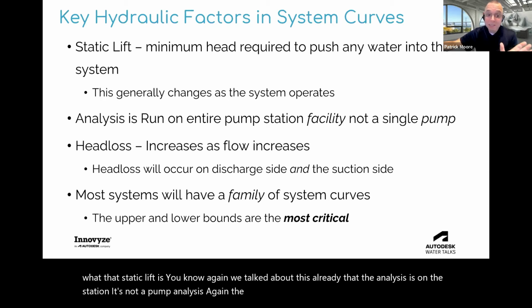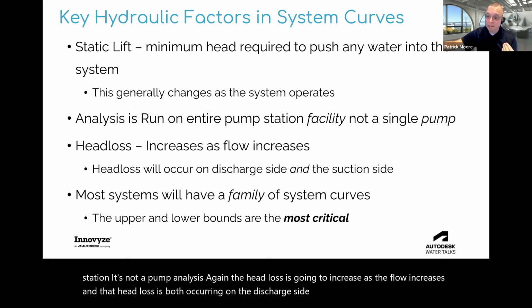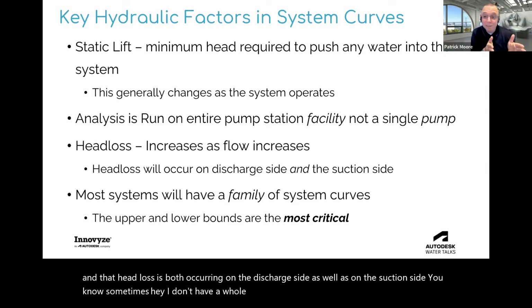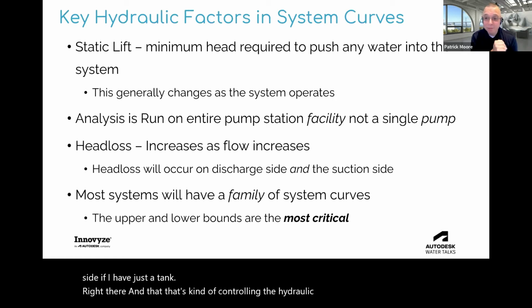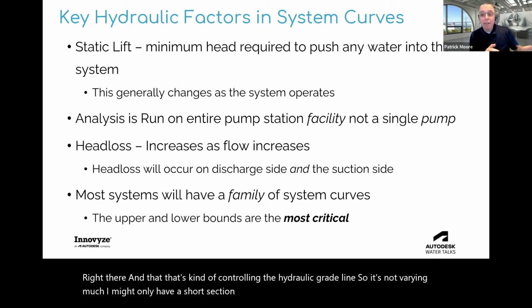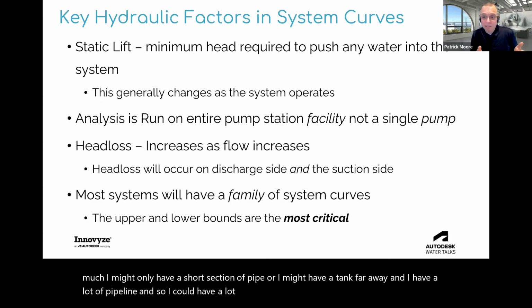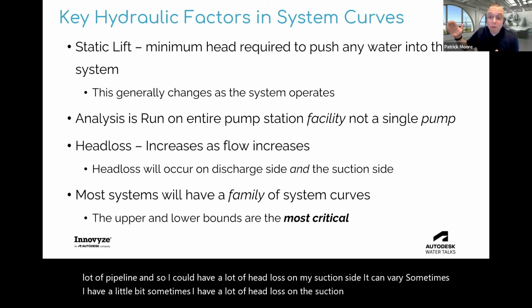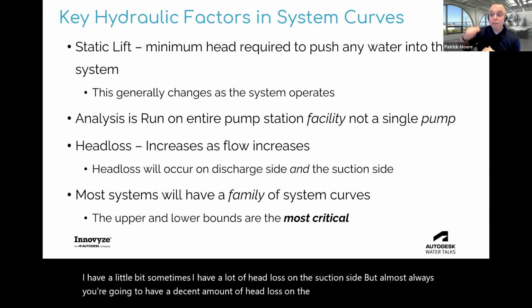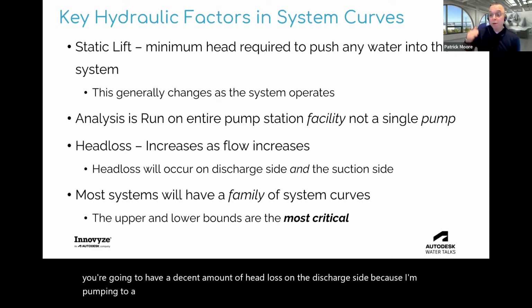Again, the head loss is going to increase as the flow increases. And that head loss occurs both on the discharge side as well as on the suction side. Sometimes I don't have a whole lot of head loss on my suction side if I have just a tank right there, controlling the hydraulic grade line, so it's not varying much. I might only have a short section of pipe, or I might have a tank far away and a lot of pipeline, and so I could have a lot of head loss on my suction side. It can vary. Sometimes I have a little bit, sometimes I have a lot of head loss on the suction side, but almost always you're going to have a decent amount of head loss on the discharge side, because I'm pumping to a receiving tank most of the time, or pumping to my far customer and I need to maintain some minimum pressure for them. That's usually what's governing in all those.